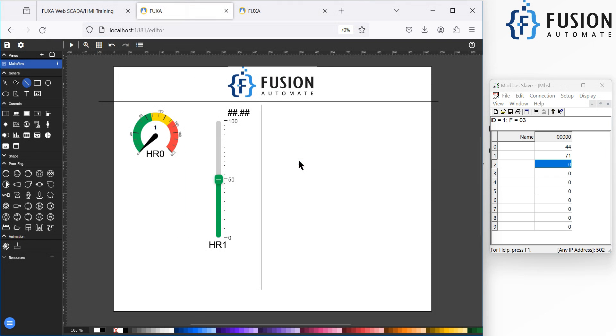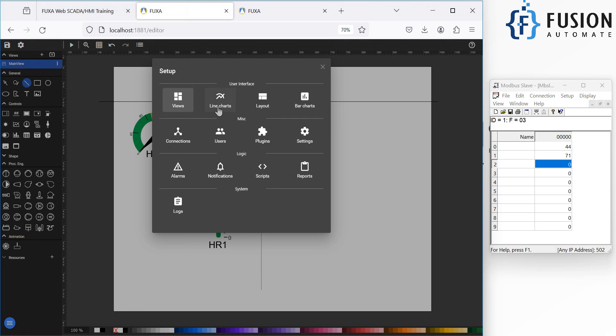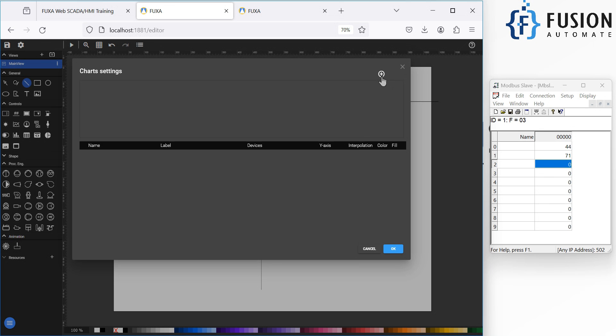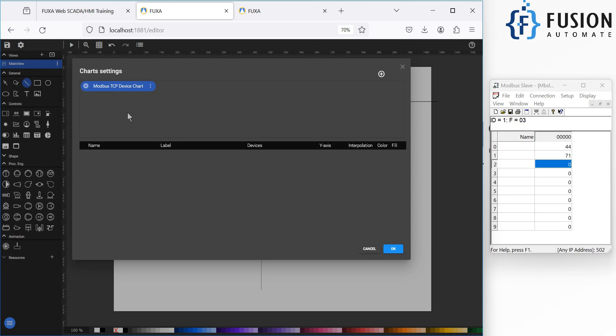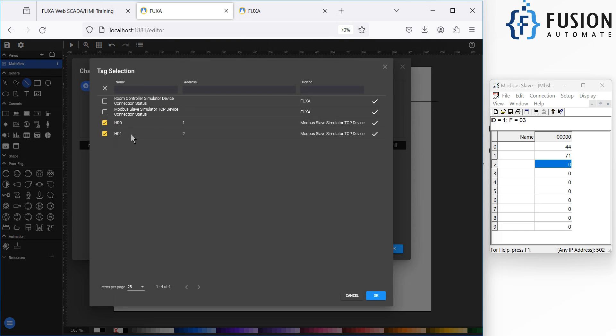To do this, navigate to the editor first, then click on Edit Project. Go to Line Chart and click on the plus icon. Provide the name of your chart — here it is 'Modbus TCP Device Chart' — and press OK. After that, we need to add the tags for which we want to generate the trend. Click the three-dot menu, click Add Line, and select the tags you want to add inside the trend. I have selected these two variables, hr0 and hr1.